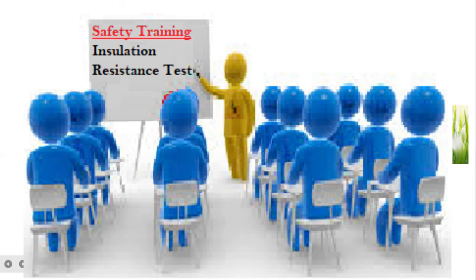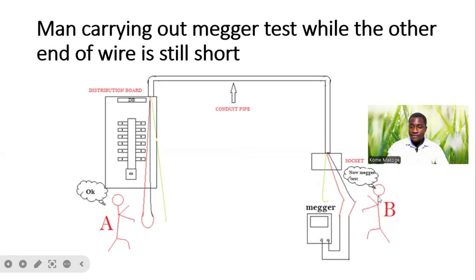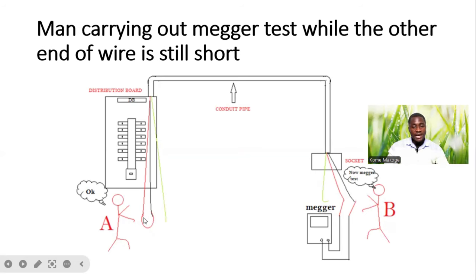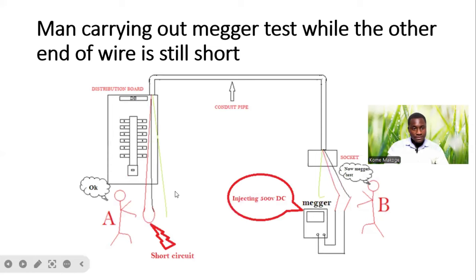As I said, trained personnel should carry out this test. If he is to carry out the test, he needs to properly inform the other person that they are beginning with the megger test or insulation resistance test. The person at the DB side needs to know to remove the wire that was used to short both ends. Let's see what happens.